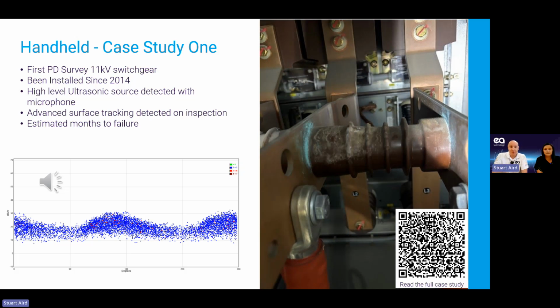So in that case, we've been there and done that PD survey and picked it up with a handheld device. I think the thing we can think, though, is that we were a little bit lucky. We were lucky that we got there at that particular time. We have monitored things like this type of failure, surface related partial discharge. We can see in the picture on the right we've got surface tracking. The bushing between the two live conductors is getting a considerable track across it.